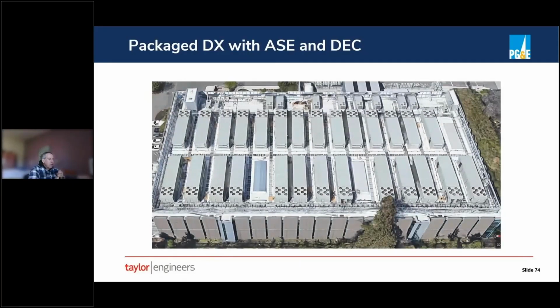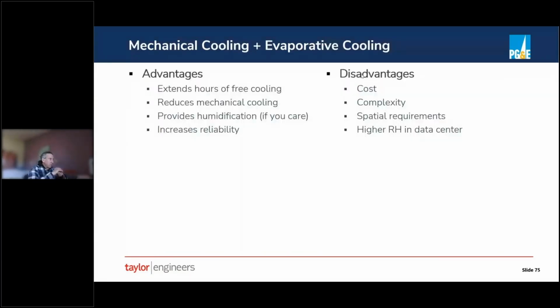This is a data center we've worked on for a few years. It wasn't our design originally, but we've done a lot of troubleshooting and upgrades to it. It's using packaged rooftop units, DX boxcar units that you might see in an office. But as you can see, the roof is packed with them to meet the high loads in this data center. This one has both ASE airside economizing and DEC direct evap cooling. So it has mechanical cooling, but also free cooling with outside air and, what I would argue is free cooling, using direct evap. So it's a very efficient system for much of the year. Almost never need mechanical cooling.